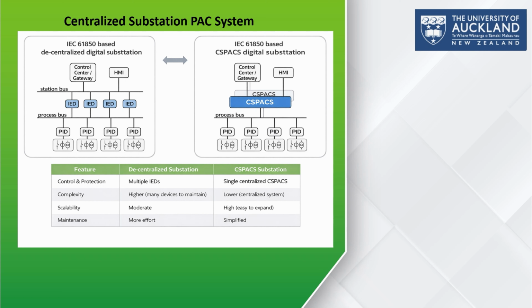On the other hand, the centralized substation protection digital substation replaces multiple IEDs with a single centralized platform. Right? The control center or gateway and HMI operates similarly, connecting to the centralized substation to manage operations and provide visualizations. Field devices still interface through PIDs, but all protection, control, and metering functions are centralized within the CSPACS. This centralization reduces hardware complexity, simplifies maintenance and configuration, and improves interoperability with other digital substation systems.